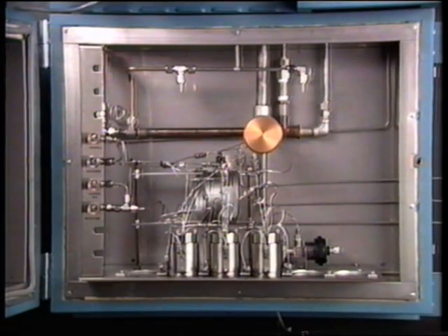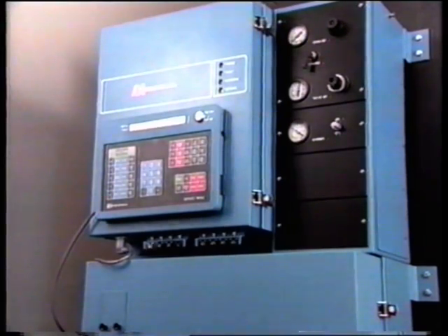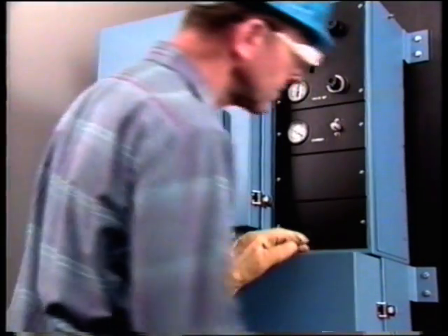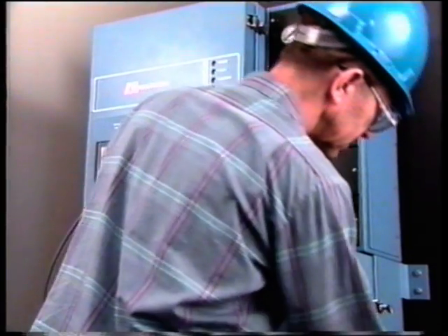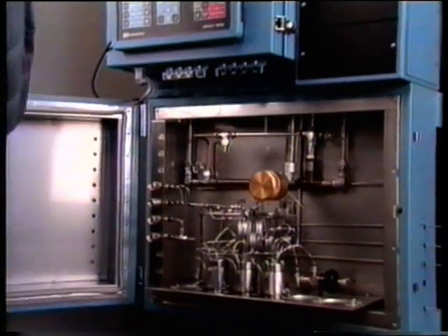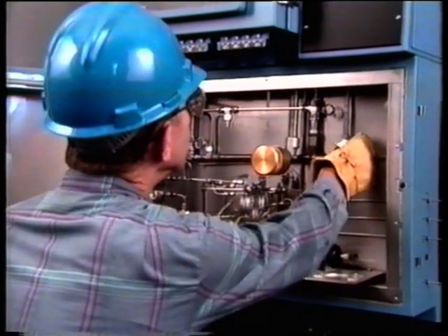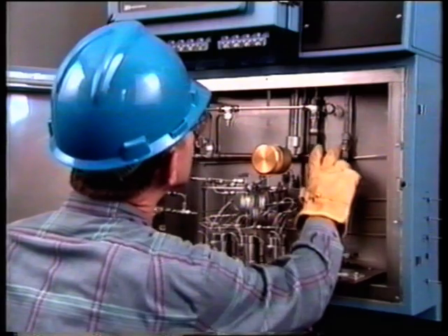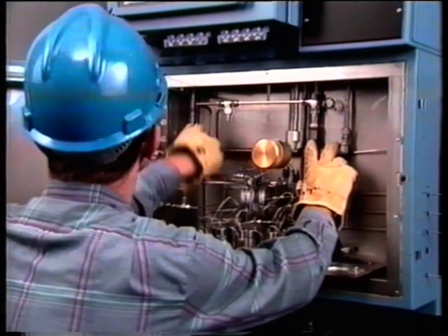In the air bath oven, heated air circulates inside a thermally insulated enclosure. An electrical heater and thermostats monitor and control the oven temperature for safe operation. To expose oven components for maintenance, loosen any latches or bolts that are securing the cover. Examine the inside of the oven for cleanliness. Debris may indicate that the air being circulated through the oven is dirty. There should be no traces of water, oil, or dirt in the oven.